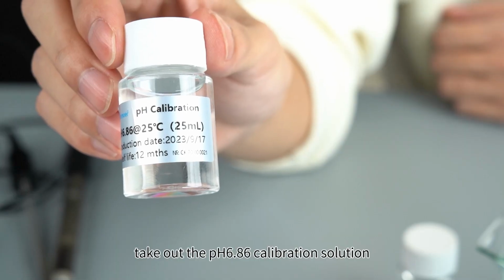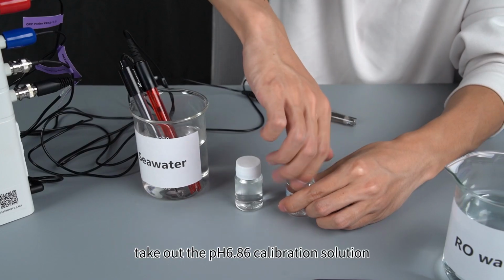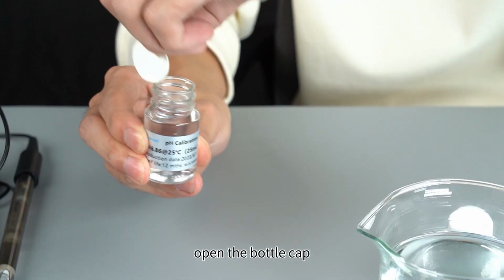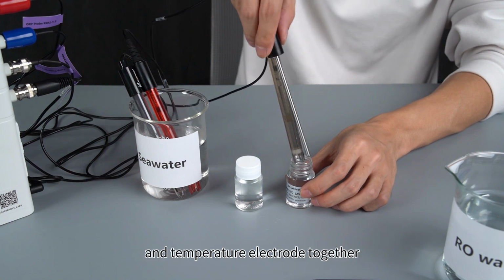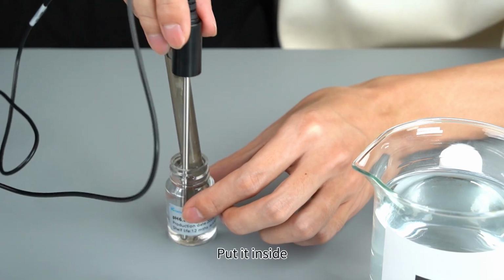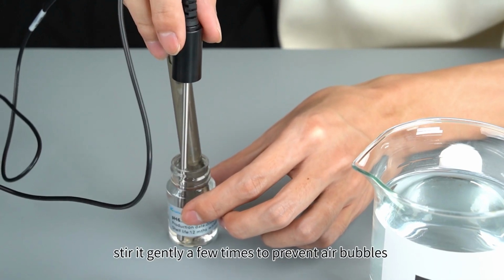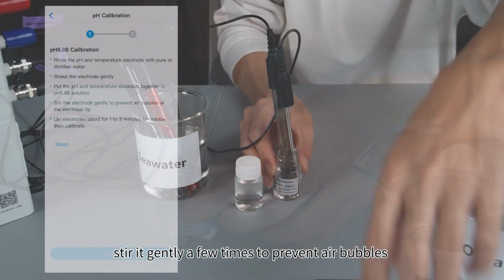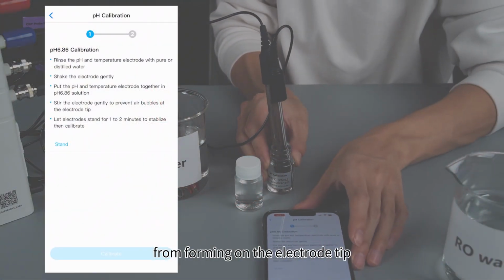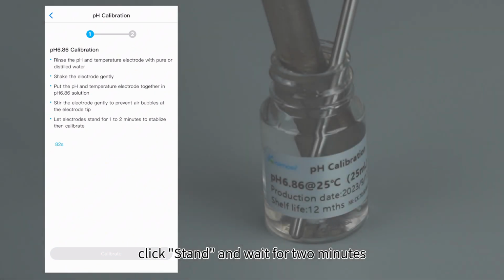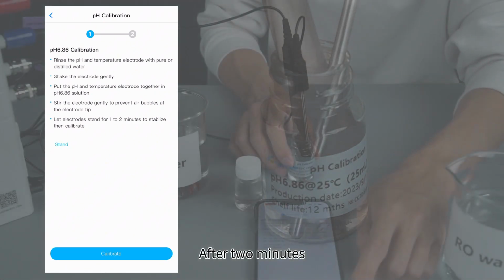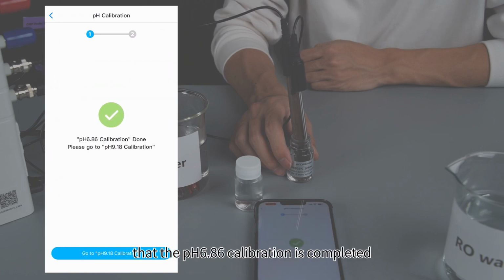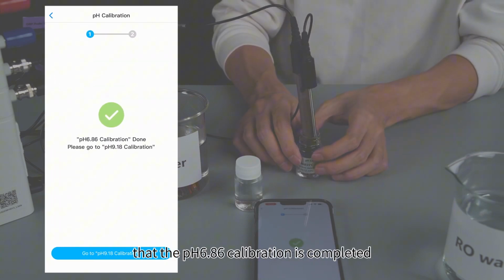Take out the pH 6.86 calibration solution, open the bottle cap, and put the pH electrode and temperature electrode together inside. Stir it gently a few times to prevent air bubbles from forming on the electrode tip. Click Stand, and wait for 2 minutes. After 2 minutes, click Calibrate, and the page shows that the pH 6.86 calibration is completed.